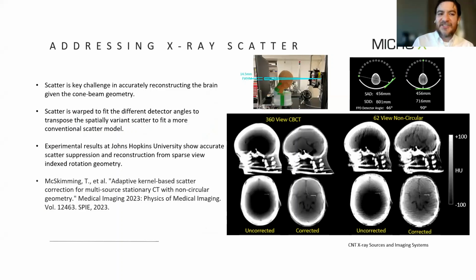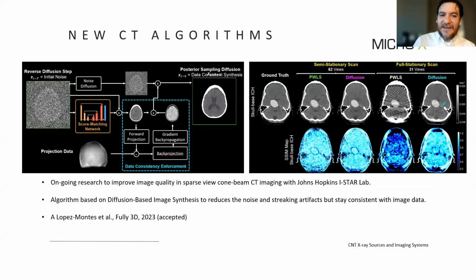Additional work has been done and published, specifically looking at the scatter. In this geometry, the detector is curved and the angles are not the typical cone beam 90-degree orthogonal angles. There are some interesting odd angles. So adjusting the scatter for that spatial variance and correcting it has been a huge amount of work, so that we can get an accurate cone beam CT reconstruction. And then finally, we're now looking at ongoing research into new imaging algorithms, diffusion-based synthesis, to improve the reconstruction beyond a typical model-based reconstruction. How good can we get a few view cone beam CT to really pull out the small hemorrhages in the brain?